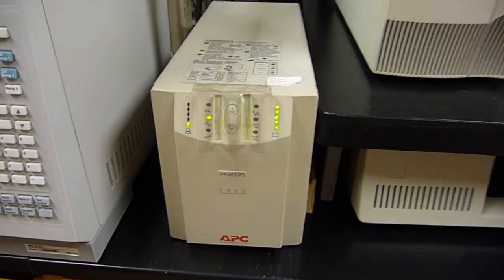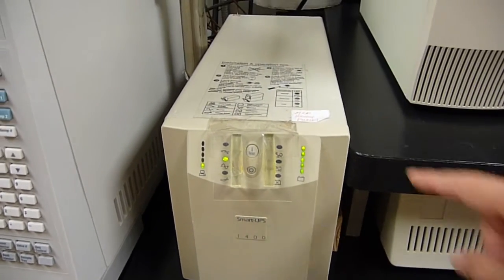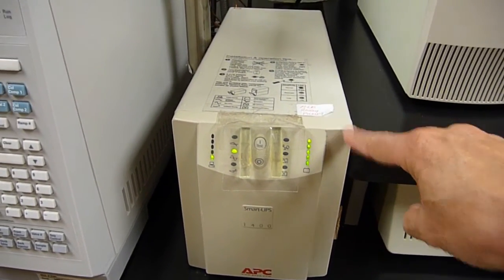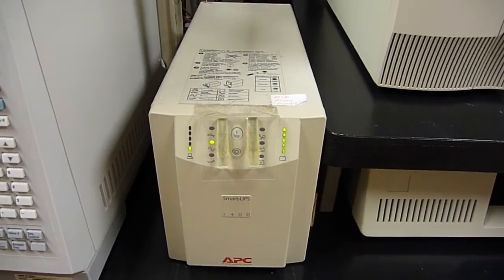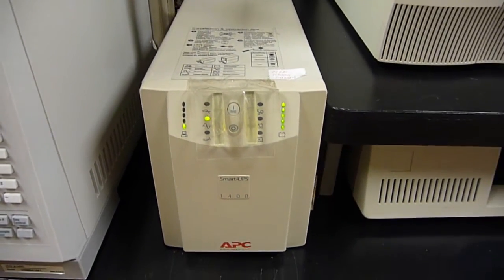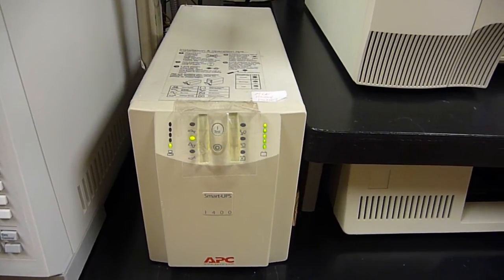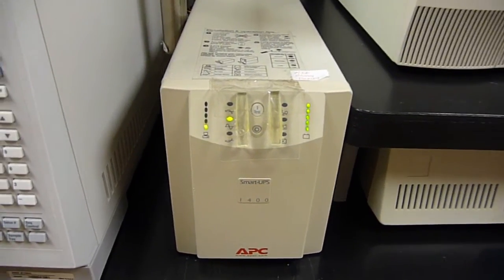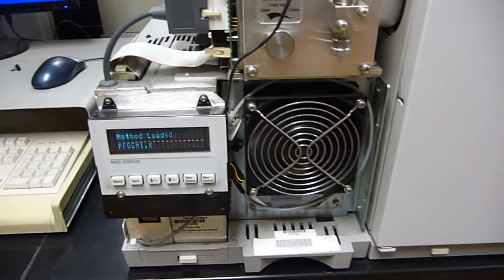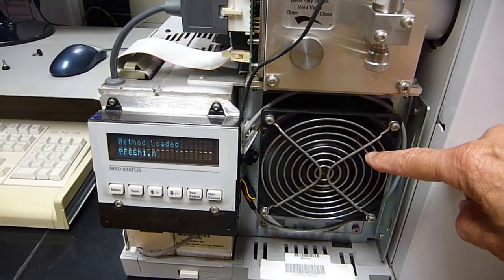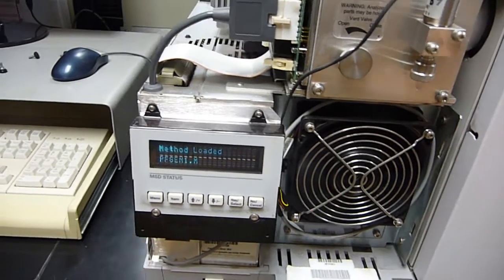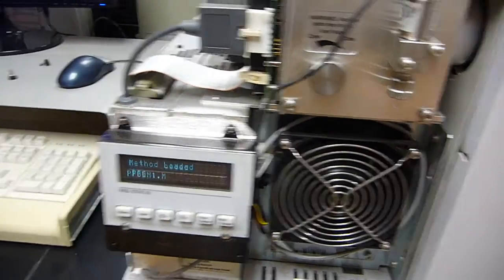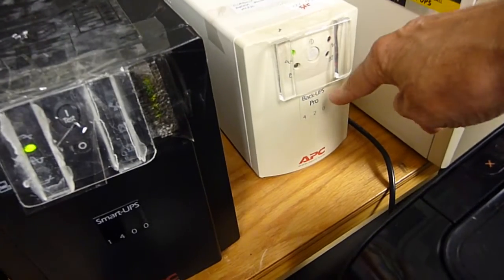So the rough pump has its own separate UPS, 1400 watts. Right? The power gets cut. This baby will keep that rough pump going 20 to 30 minutes, long enough for the diffusion pump to get nice and cold. Separate UPS for the cooling fan. To keep a fan going, you don't need 1400 watts. So we only have a 420 watt UPS for that.